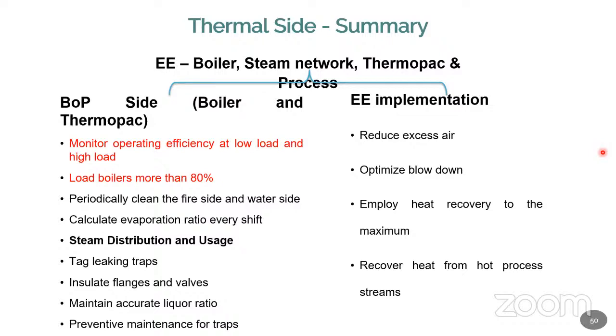When you're operating at low pressure, automatically your efficiency will drop down. Under that condition, you may club your activity, so plan accordingly. You can use a smaller boiler to operate. Instead of operating a very huge boiler for a low pressure application, you can have a separate boiler with a small capacity for a low pressure application.